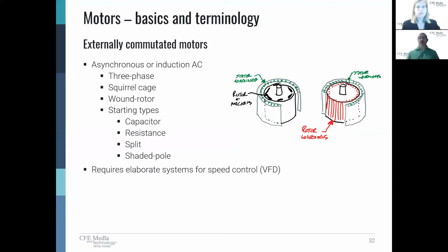Now, a motor works technically by just simply changing or generating magnetic fields that causes a rotational energy, working off the basic concept that if I have like magnets, they repel, and if I have opposite magnets, then they attract. So by simply varying the magnetic field, I'm able to generate that rotational inertia and generate rotation. Now, the primary difference between an induction motor, also called asynchronous, and a synchronous motor is the construction and how they get started. An induction motor is essentially self-starting.